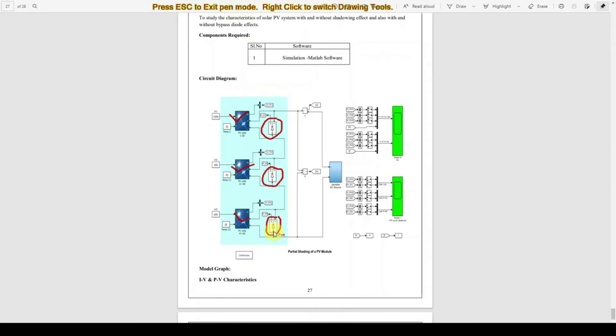During partial shading — partial shading means some panel will be shaded, that is some portion will be covered by a tree or some paper. What happens is the current flow will be blocked in that solar PV cell. During that time we need to bypass the current, and that is why we use the bypass diode. If we do not use the bypass diode, the panel will be heated heavily because some portion is blocked, and the current flow will be blocked in that PV panel.